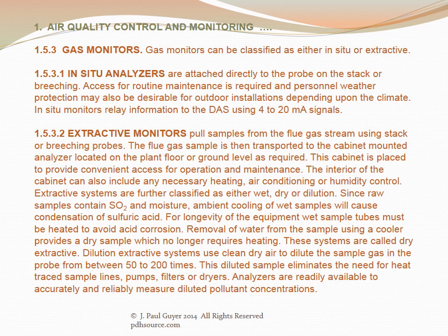Extractive monitors pull samples from the flue gas stream using stack or breeching probes. The flue gas sample is then transported to the cabinet-mounted analyzer located on the plant floor or ground level. This cabinet is placed to provide convenient access for operation and maintenance. The interior of the cabinet can also include any necessary heating, air conditioning, or humidity control. Extractive systems are further classified as either wet, dry, or dilution.